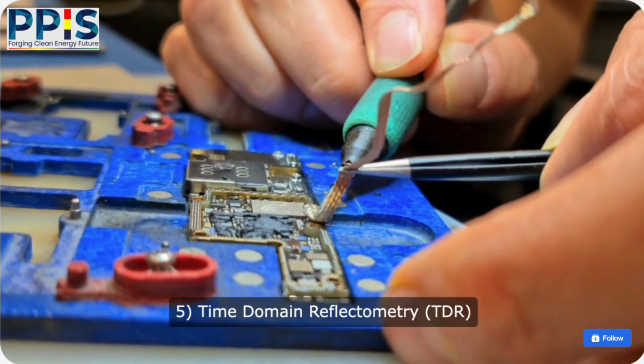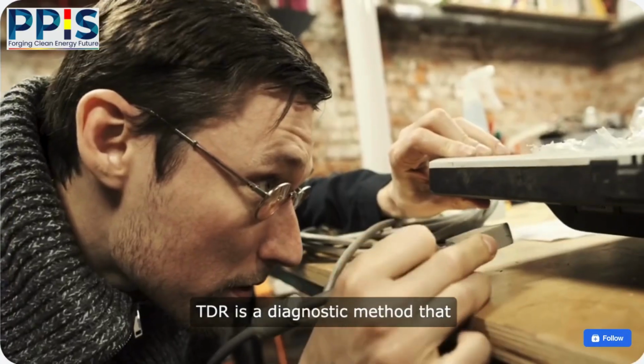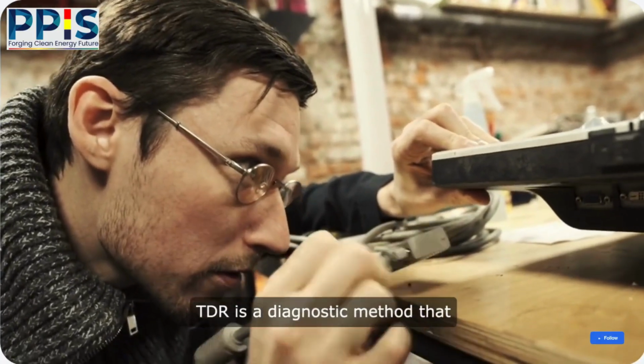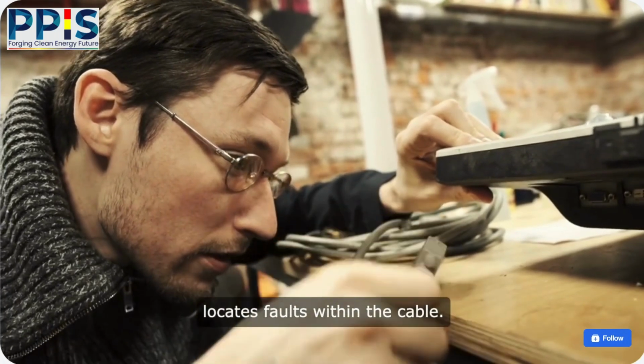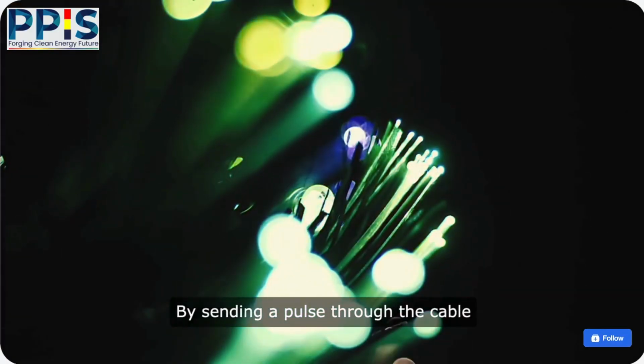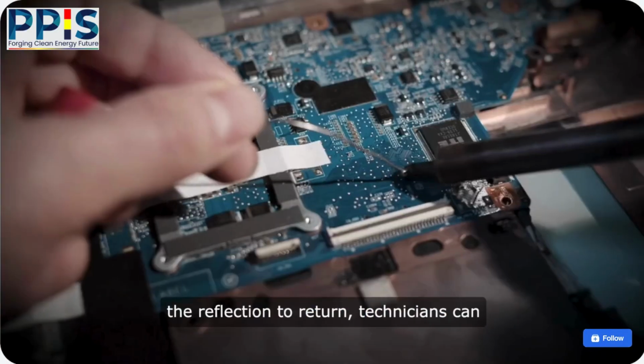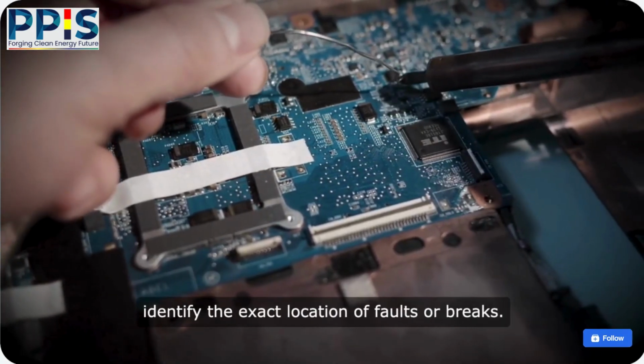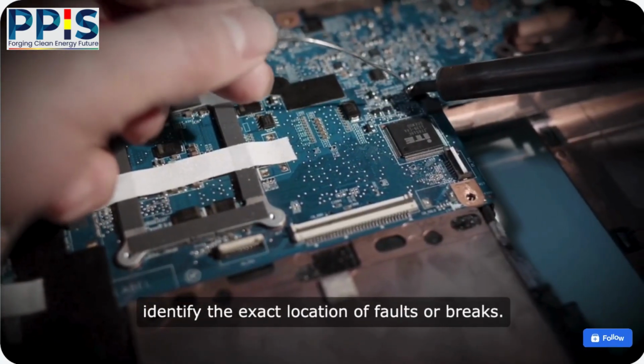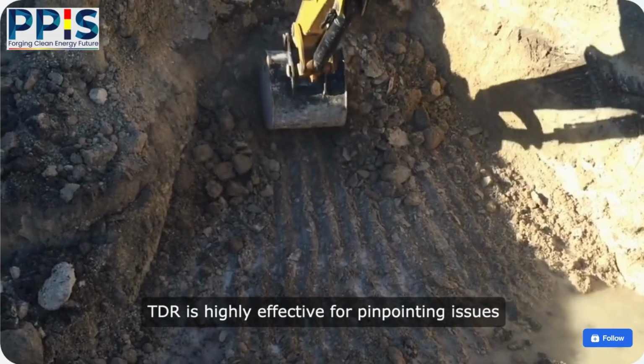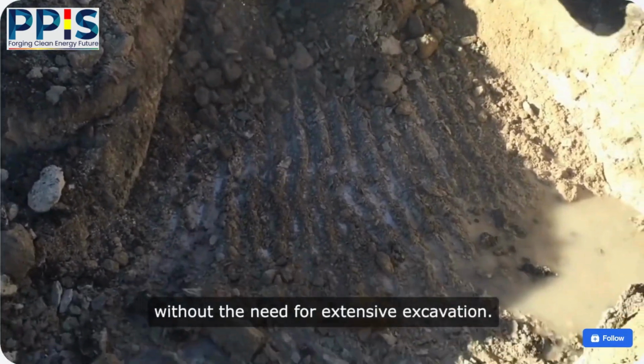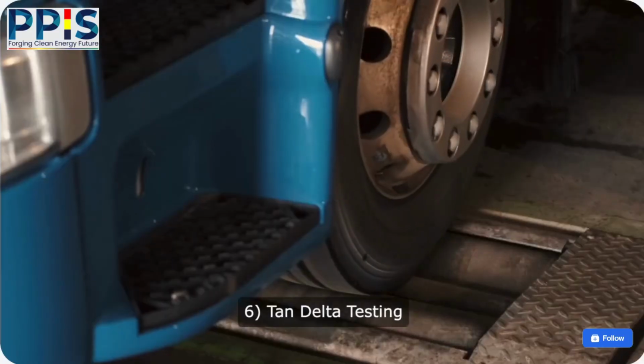5. Time domain reflectometry, TDR. TDR is a diagnostic method that locates faults within the cable. By sending a pulse through the cable and measuring the time it takes for the reflection to return, technicians can identify the exact location of faults or breaks. TDR is highly effective for pinpointing issues without the need for extensive excavation.